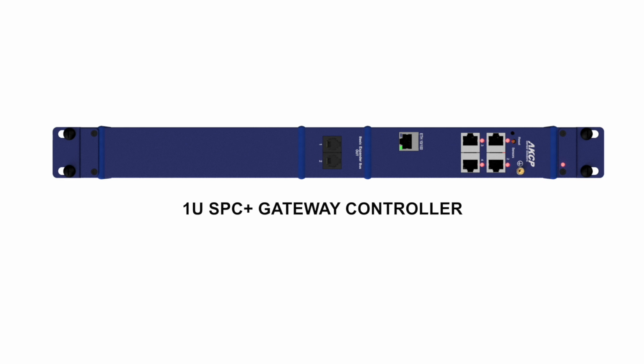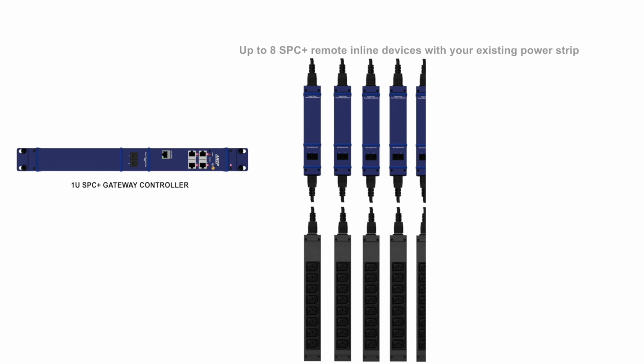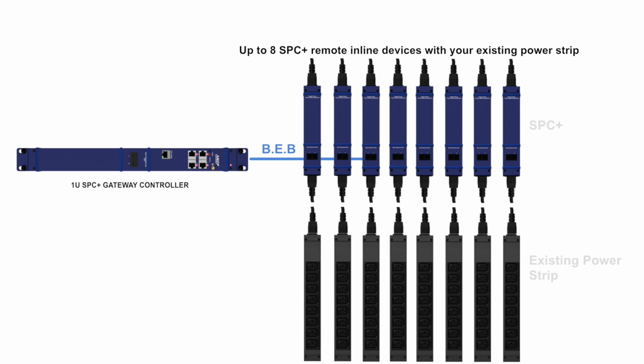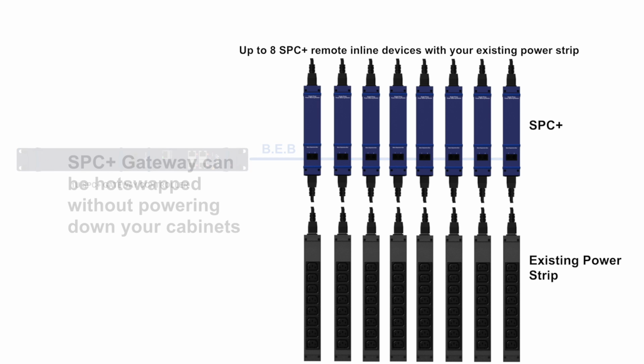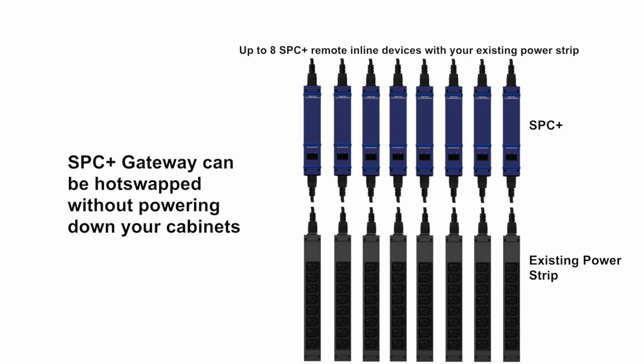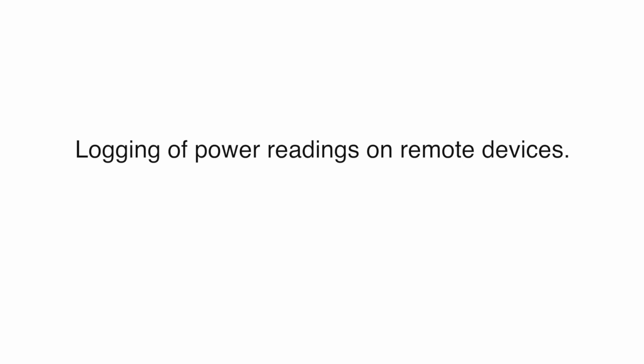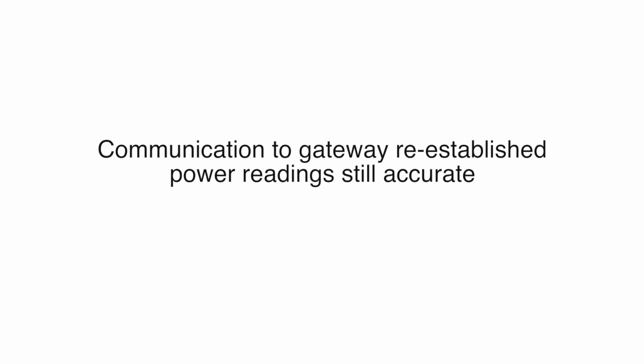An alternate setup is to use a 1U mounted independent gateway controller, and this connects together with 8 SPC Plus remote devices. The advantage of this configuration is that the gateway is a truly hot swappable controller. Should the controller need servicing, it can be removed without any interruption to the power of your other cabinets. SPC Plus remote devices will even continue to log total active power locally, so when communication is re-established, your power data is still accurate.